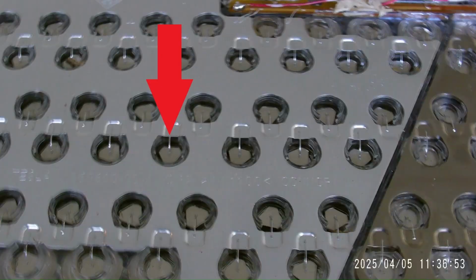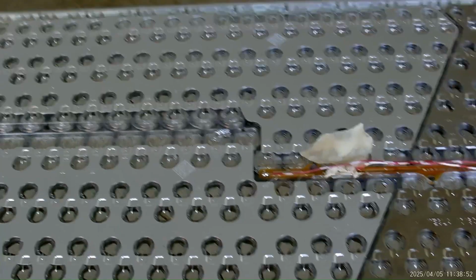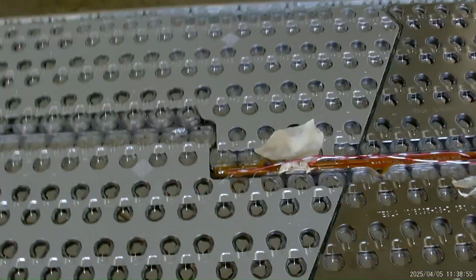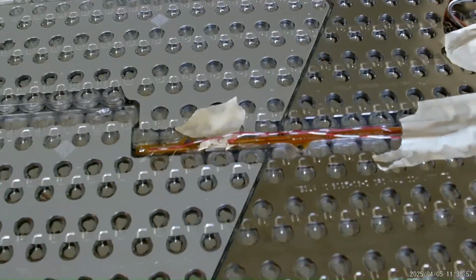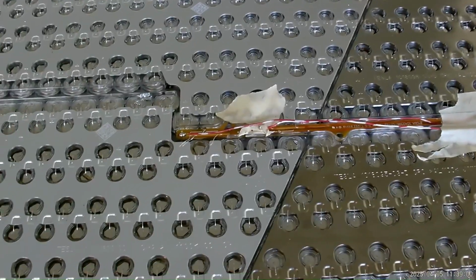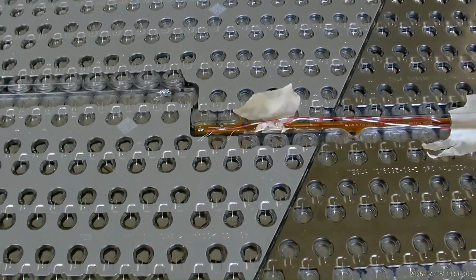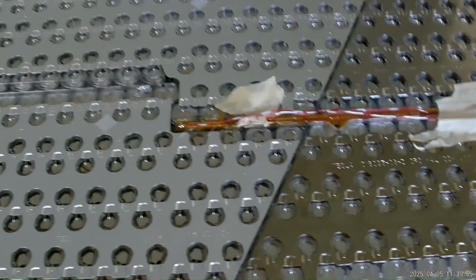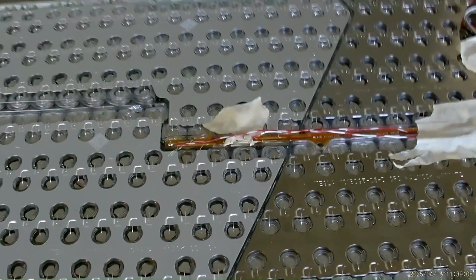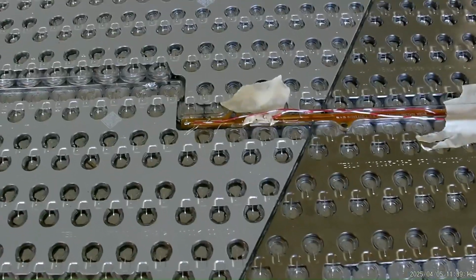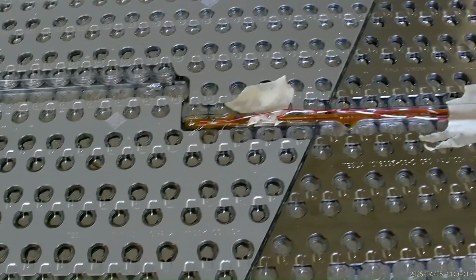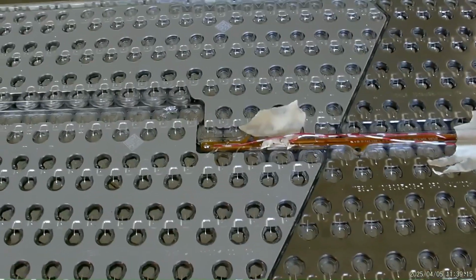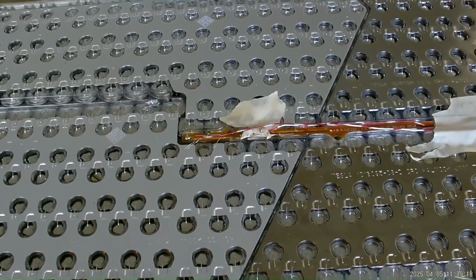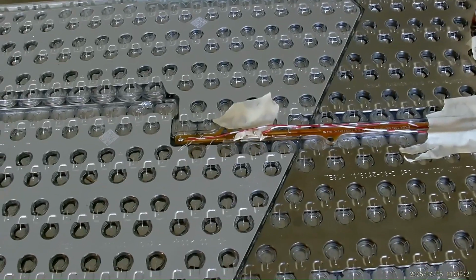Each cell has a little wire, which is also a fuse link, attaching the battery electrically to these metal sheet conductors. You can see how the sheet conductors are separated. On this side of the battery, we have 3 conductors, and on the other side, we have some more. All in all, it puts them in series parallel, such that a bunch of batteries are in parallel with each other, and then that bank is in series to add up to 24 volts.